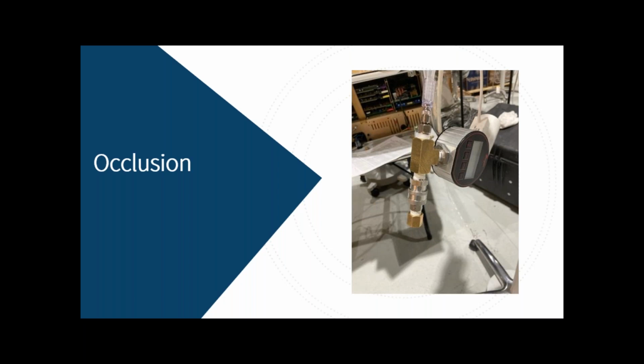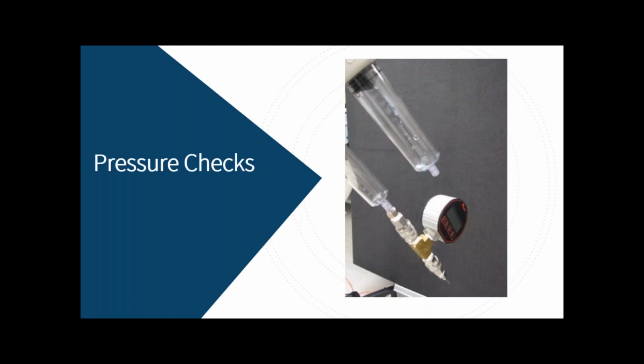Not much different than an IV pump. Pressure checks. There's your gauge, and we have to put some type of restriction on there to create back pressure to see what that pressure is. Not much different than an IV pump, but it is because we're dealing with a lot more pressure, a lot more volume, a lot faster flow rate, and they don't have 50 of them in the hallway or in the closet that they can pull out another one and swap out. They have one per CT, one for MR, one for cath lab. They have one.